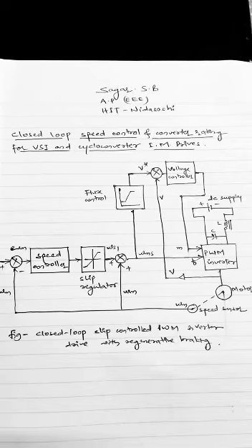But it is ensured that the motor operation always occurs in the portion of the speed torque curve between synchronous speed and the speed at the maximum torque for entire frequencies. Thus, a high torque to current ratio can be ensured in this region.